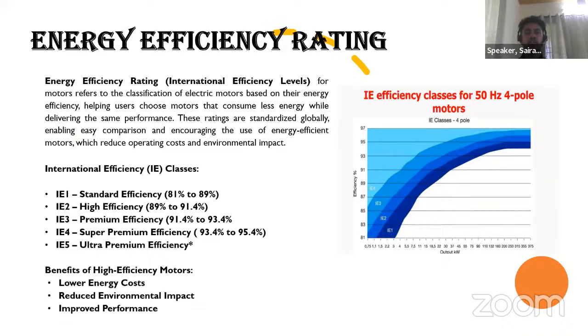The efficiency rating of the IE1, the standard efficiency, will vary from 81 to 89%. Eventually, the high efficiency motors, premium efficiency motors, super premium efficiency. Slowly, the motors are getting replaced in the industries from IE1 or IE2 to IE3 or IE4 based on their requirements.